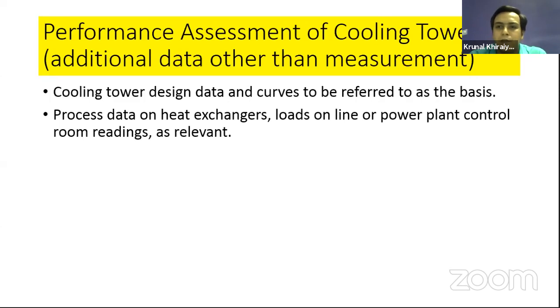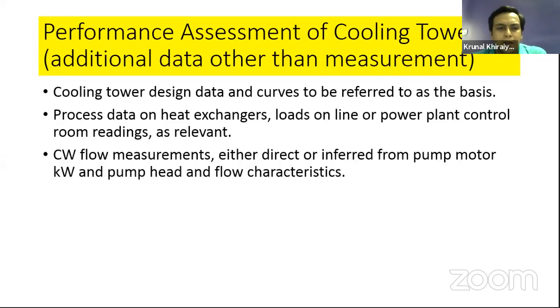Yes, it means you need to compare all the performance parameters with the rated or the design parameters. Process data on the heat exchanger load and the line power plant measurements and room readings, as well as other relevant data. Cooling water flow measurements, either direct or indirect, pump motor kilowatt and pump head, then the flow characteristics curves that you need to measure.